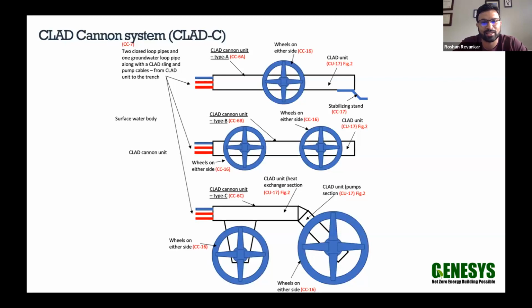An interesting application that we have developed is what we call the CLAD cannon systems. The entire assembly does not always need to go inside a borehole. If there is surface water available, this entire CLAD assembly is on wheels and is just rolled down into a lake or a surface water body. Same 3 pipe connections to supply and return going into the heat pump side, and then a discharge, which of course in this case can just be discharged back into the lake. So this is an interesting application.